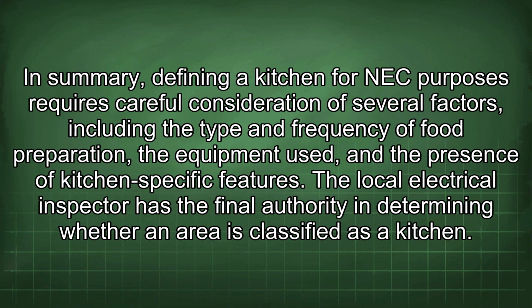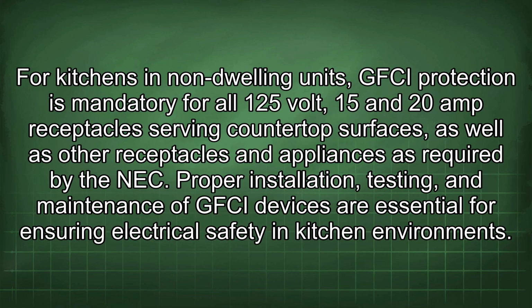In summary, defining a kitchen for NEC purposes requires careful consideration of several factors, including the type and frequency of food preparation, the equipment used, and the presence of kitchen-specific features. The local electrical inspector has the final authority in determining whether an area is classified as a kitchen. For kitchens in non-dwelling units, GFCI protection is mandatory for all 125-volt, 15 and 20 amp receptacles serving countertop surfaces, as well as other receptacles and appliances as required by the NEC. Proper installation, testing, and maintenance of GFCI devices are essential for ensuring electrical safety in kitchen environments.